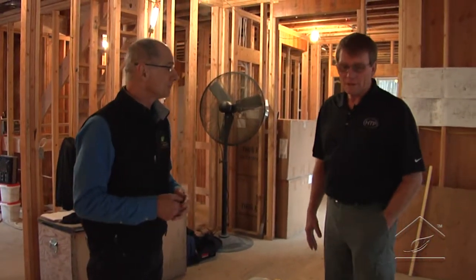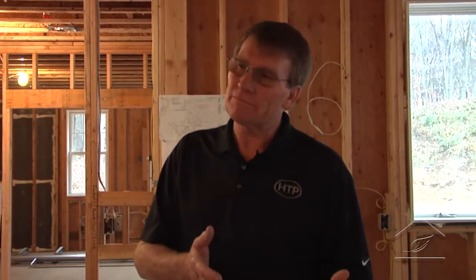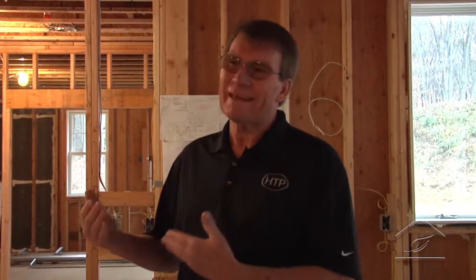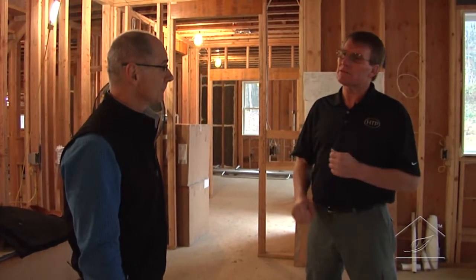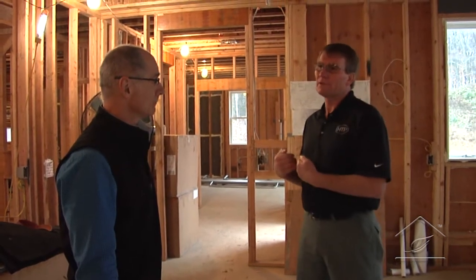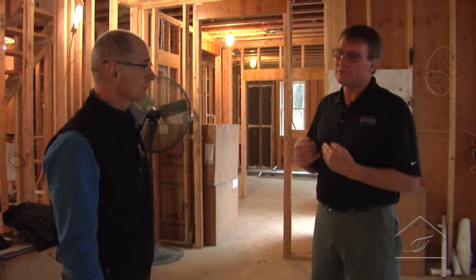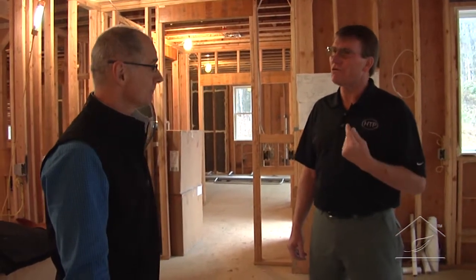Well, people come to me occasionally and say, can I just oversize my PV panel array, if I'm going to put one on, to handle my hot water load? But if you consider and measure the energy output of a PV array versus a hot water panel, hot water panels are in the 80% plus efficiency range, and PV panels have only gotten to about 20% efficiency. So if you consider a square foot of area and the energy the sun is producing, a hot water panel is much more efficient at producing exactly what you're going to use, instead of taking electrical energy and converting it into hot water. It takes about 4 kW of PV panels to heat a hot water tank for an average family. So now you've just consumed most of your PV output, just to heat your hot water.